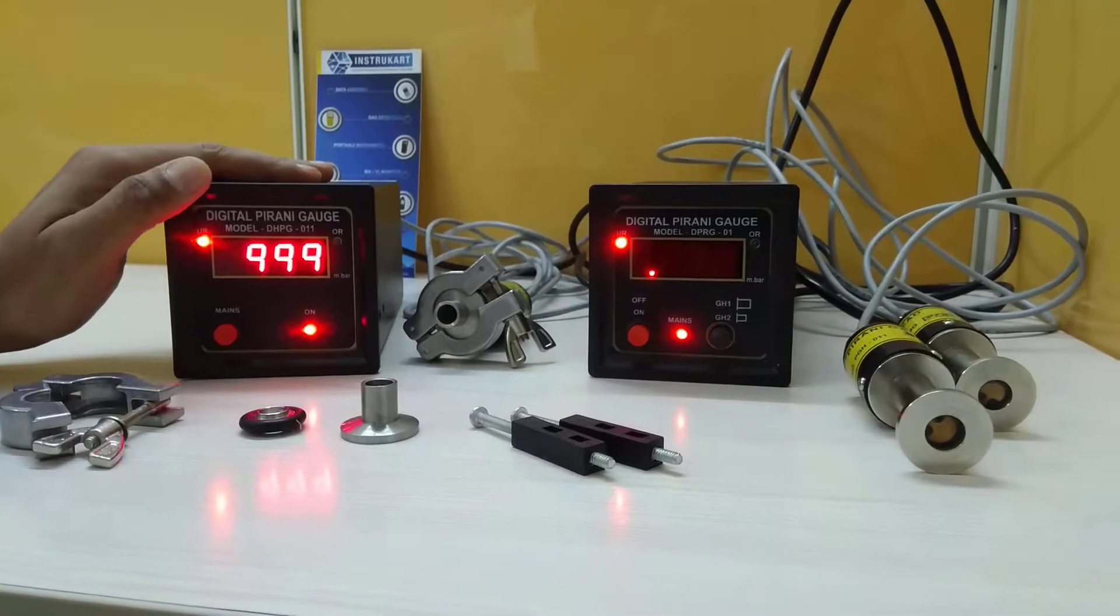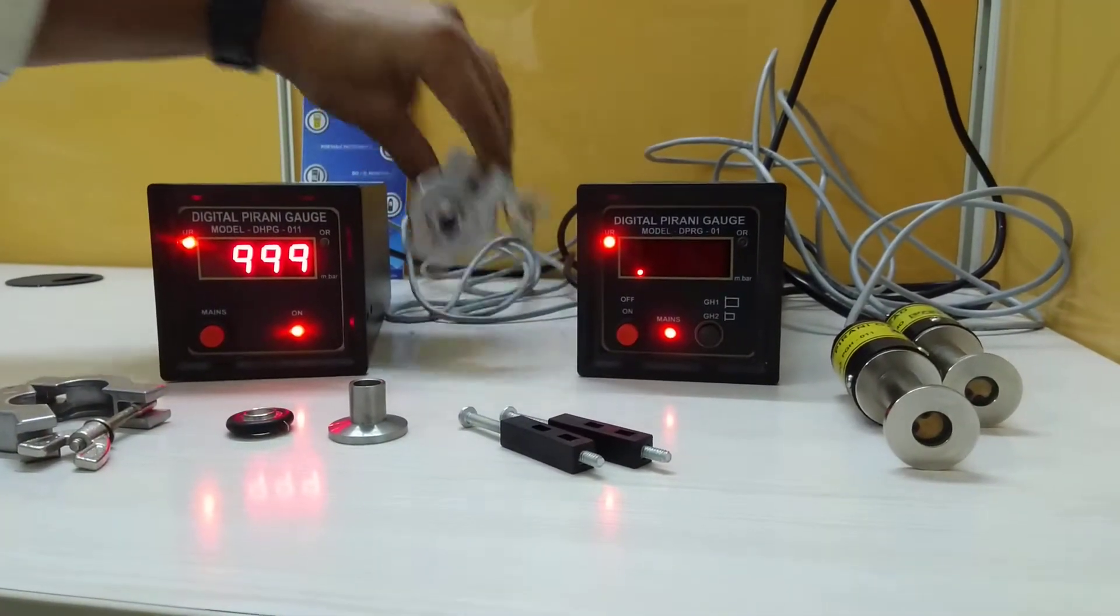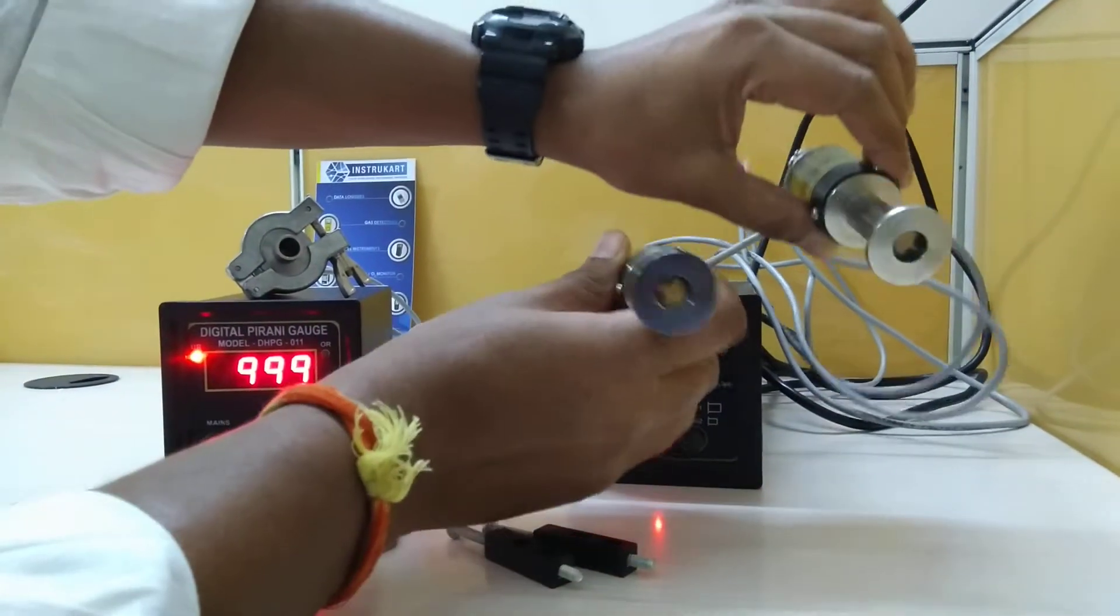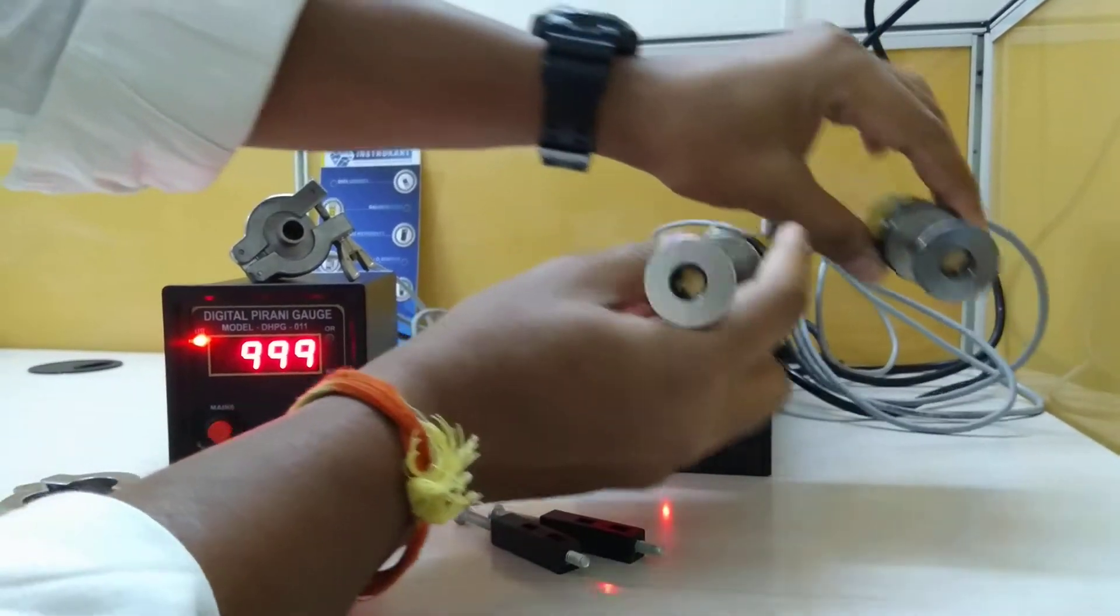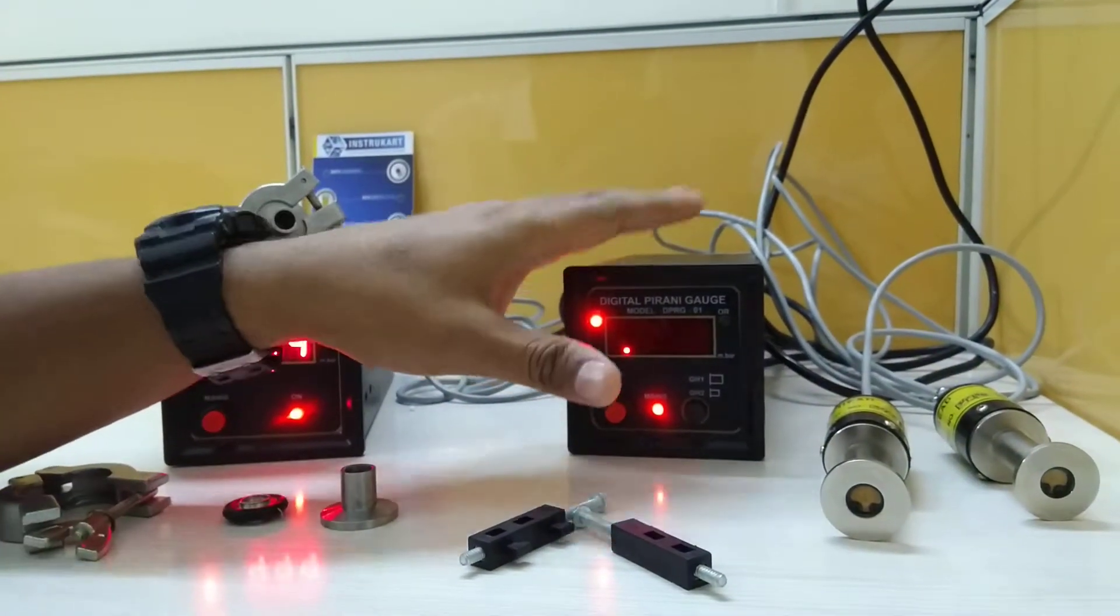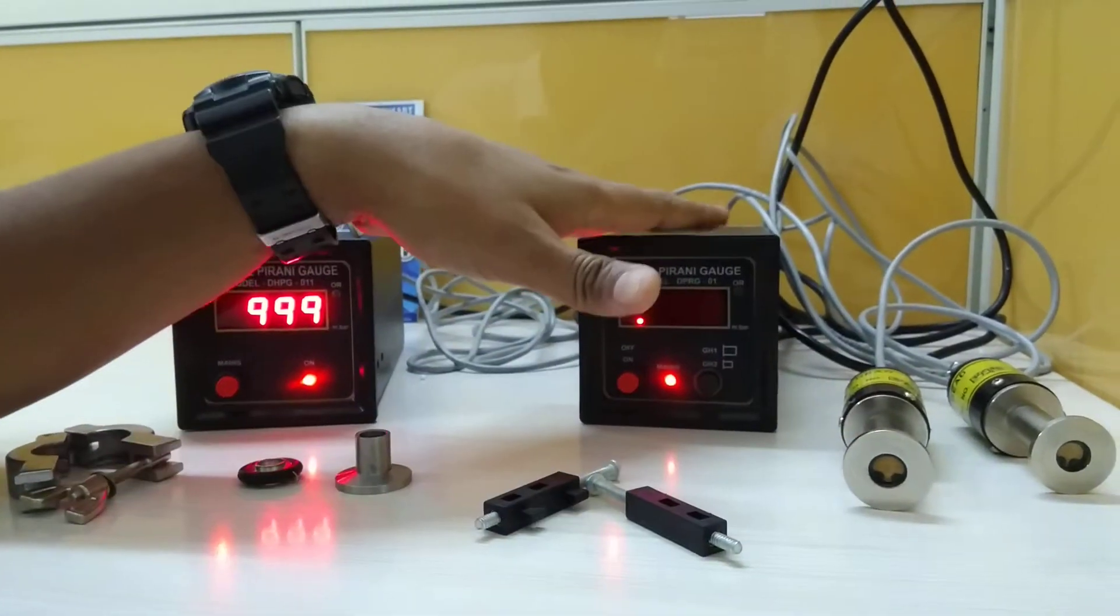The difference between these two is that we have one sensing point with this Pirani gauge, but this one has two gauge heads as you can see here. This is basically used to check two different inputs simultaneously.